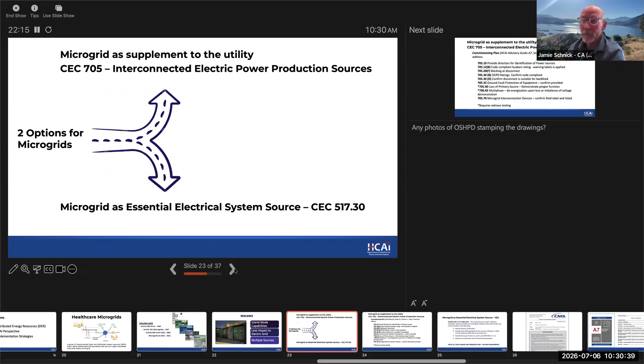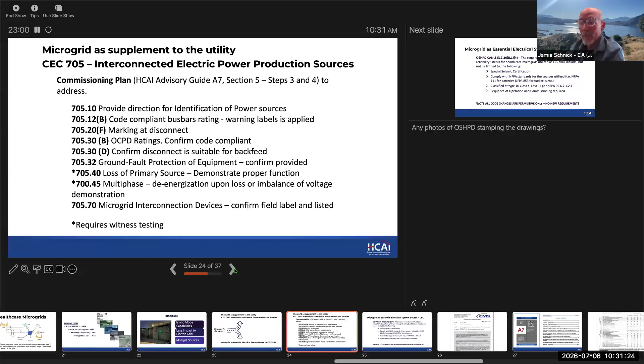There are a number of requirements to incorporate a microgrid to supplement the utility. For an existing facility, you need to identify the sources, and make sure the responding fire department knows how to de-energize the electrical system when necessary, including bus ratings and marking disconnects. These code requirements are fairly straightforward for implementing a microgrid at your facility.